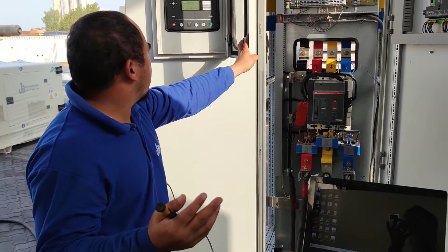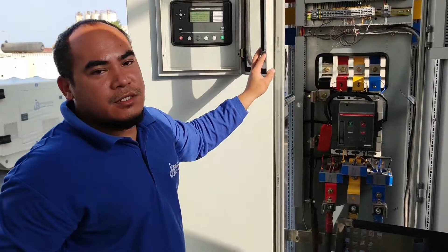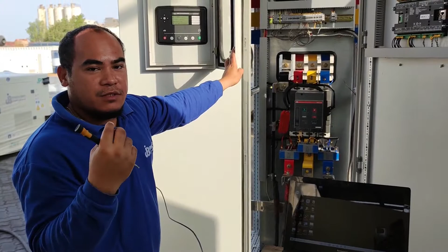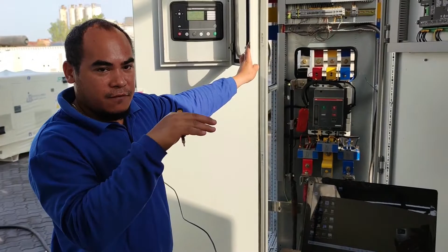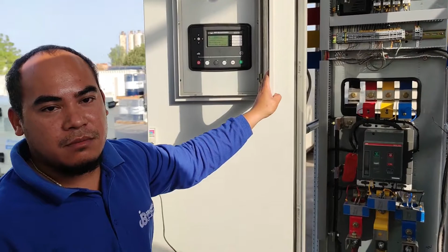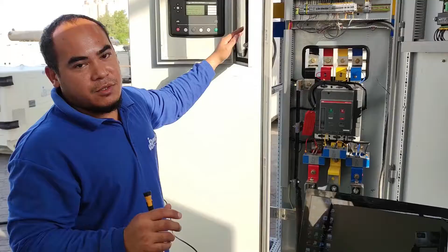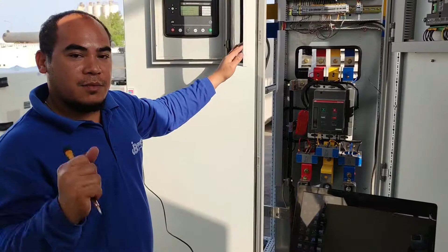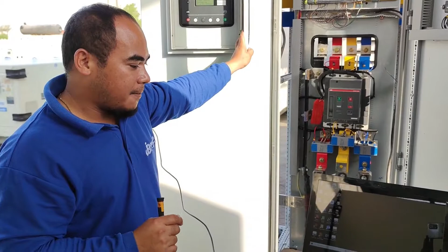Okay guys, at that time there was some alarm again. This is what we call the loading voltage and the loading frequency. Do you know what the problem is? There is no voltage going to your module. So you have to test whether there is some voltage flowing to the voltage sensing of your module. When we switched on the breaker, it went back to normal. Now we're going to start and try to do the adjustments of the voltage.